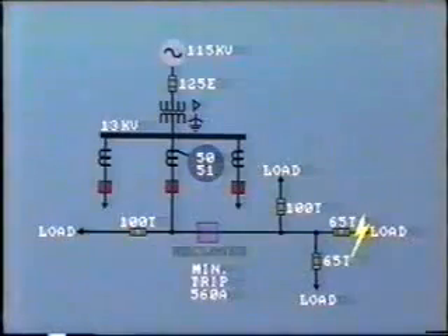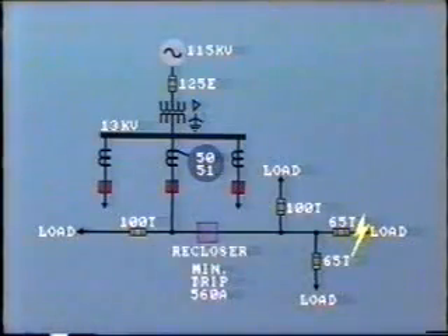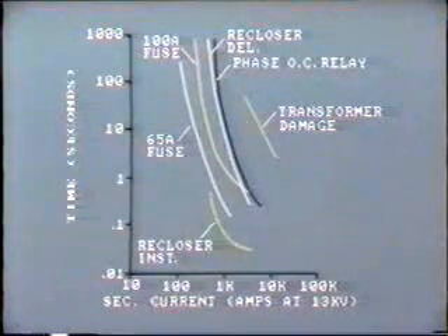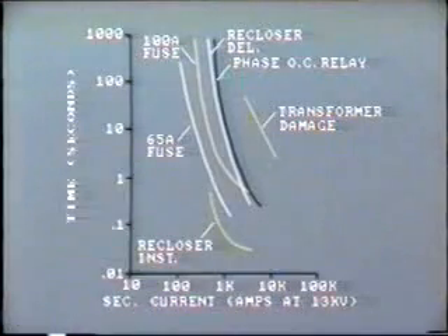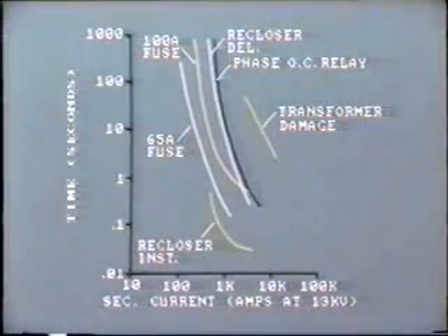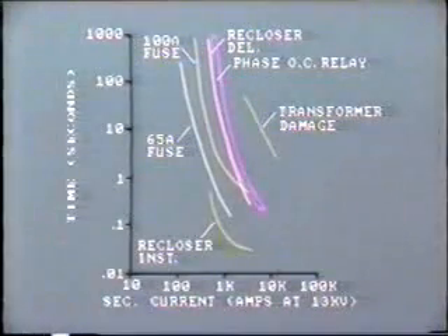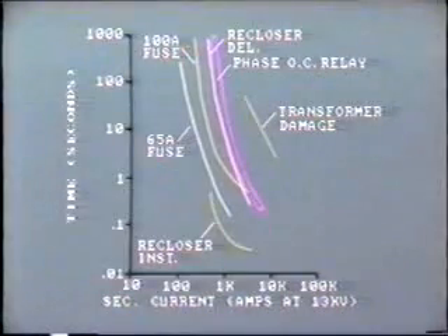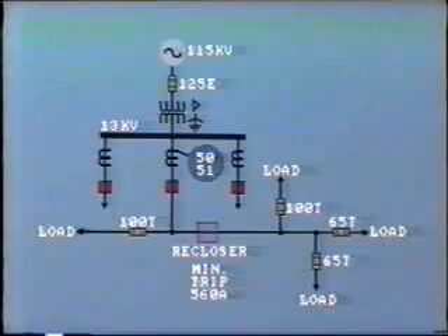If this fails to clear, that is, the recloser remains closed, then the time overcurrent relay on the feeder breaker will operate. This is set for minimum pickup of 720 amps, which is just over twice the maximum load current. The time dial is set so as to provide a time delay of at least 0.2 seconds over the recloser. There is yet further protection if all of these devices fail to operate.